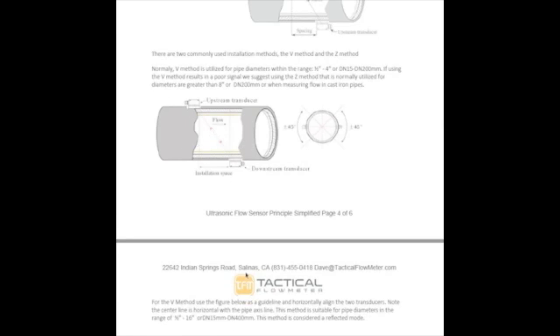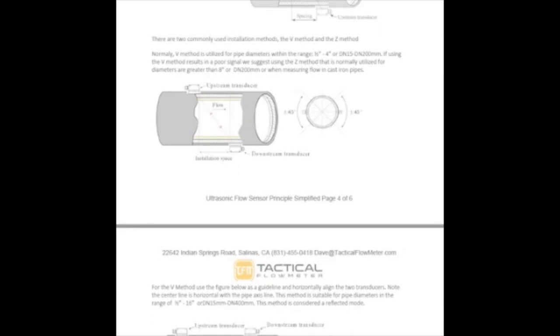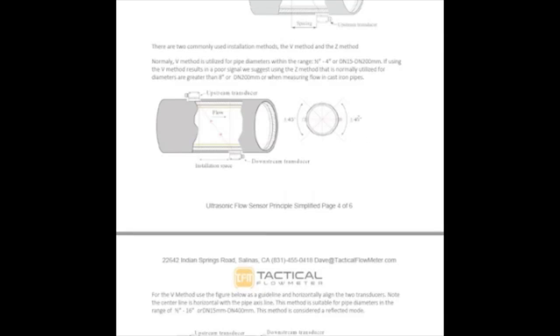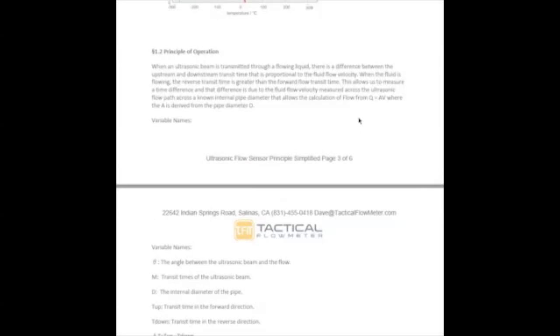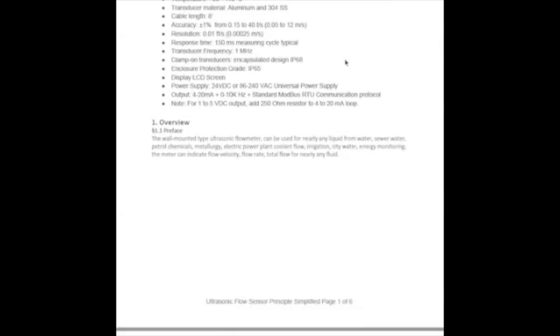And also, these things are nice that they're slightly averaging. They're taking over a path, but they don't like swirl, and they don't like air bubbles. So that's why we say up on the top here, acoustically conductive fluid with less than 5% air bubbles or solids. Those confuse it, and things ricochet off and get things all messed up.